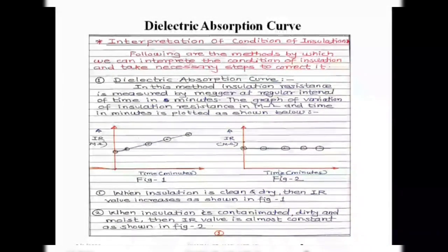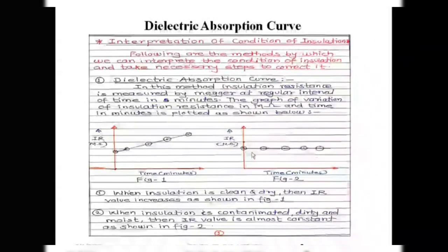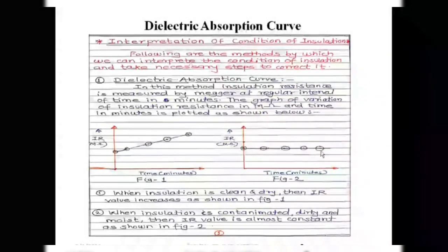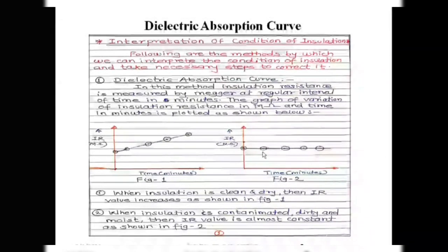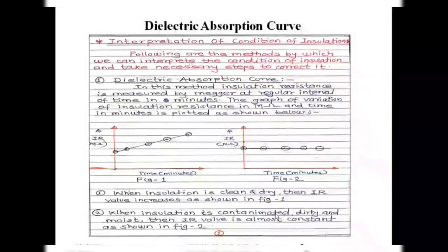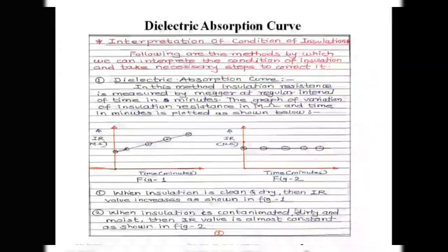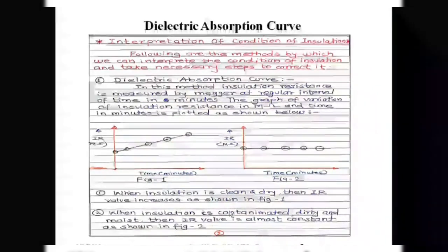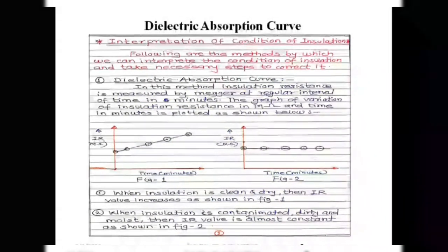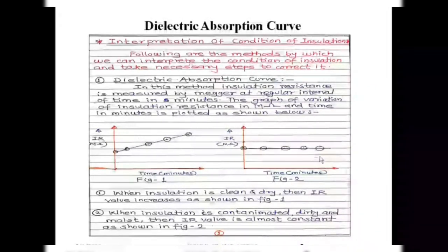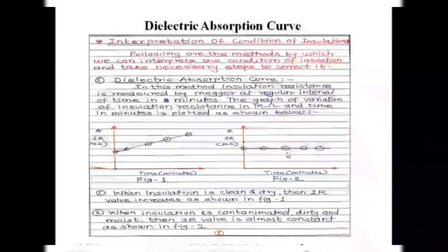Figure number two shows that the insulation resistance measured over the interval of time is almost constant — it does not increase or decrease. This means the insulation contains solid impurities, dirt, dust, moisture, or in the case of oil, dissolved gases or dissolved impurities. This kind of graph indicates that the insulation is deteriorated and weakened, and it has to be reconditioned immediately.